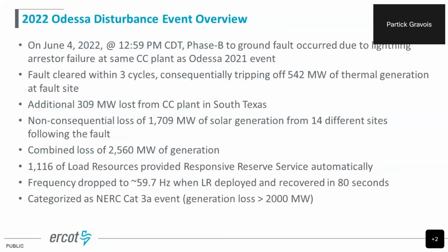We also had an additional 309 megawatts lost from a combined cycle plant all the way in South Texas. So we had to follow up with them. That was clearly some misoperations that they had at that station. They should not have tripped for a fault in West Texas. But we're not going to spend too much time on the thermal. We're focusing on the solar here.